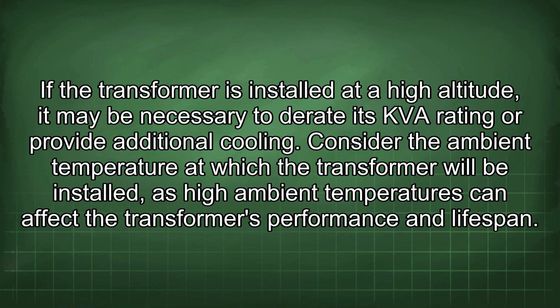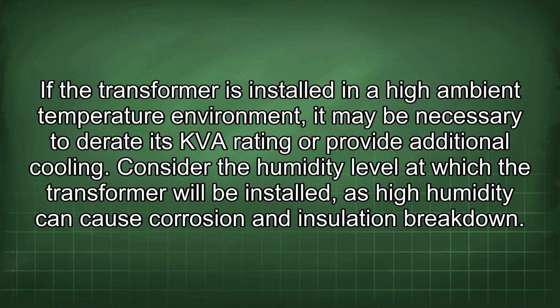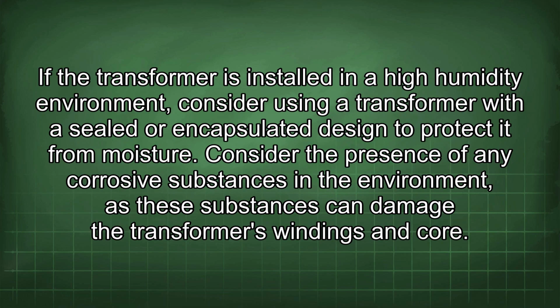Consider the ambient temperature at which the transformer will be installed, as high ambient temperatures can affect the transformer's performance and lifespan. If the transformer is installed in a high ambient temperature environment, it may be necessary to lower its KVA rating or provide additional cooling. Consider the humidity level at which the transformer will be installed, as high humidity can cause corrosion and insulation breakdown. If the transformer is installed in a high humidity environment, consider using a transformer with a sealed or encapsulated design to protect it from moisture.